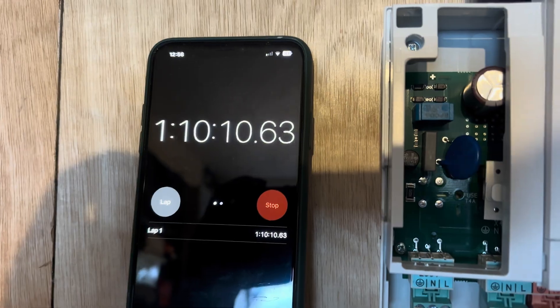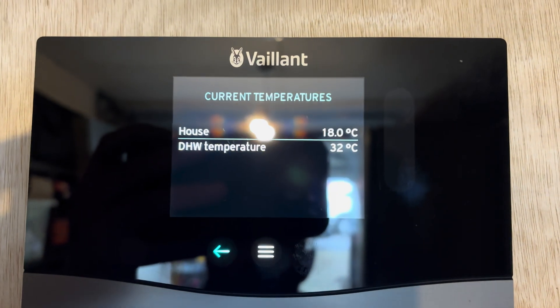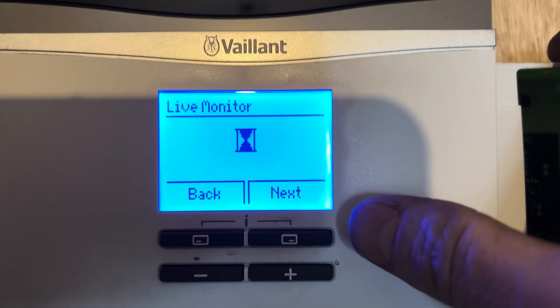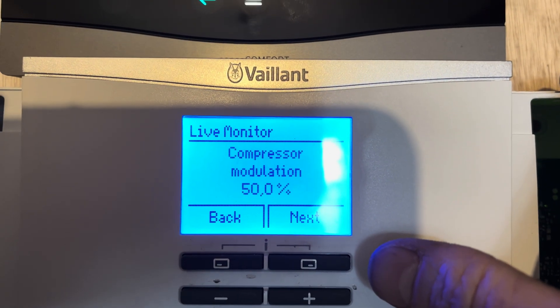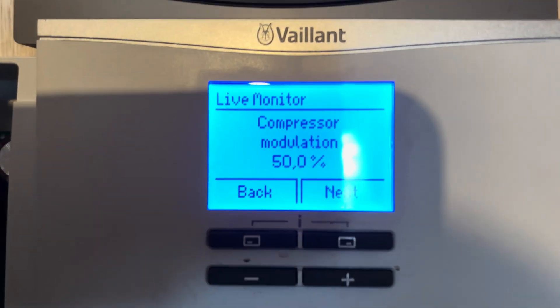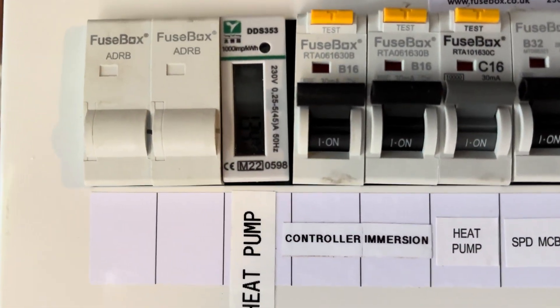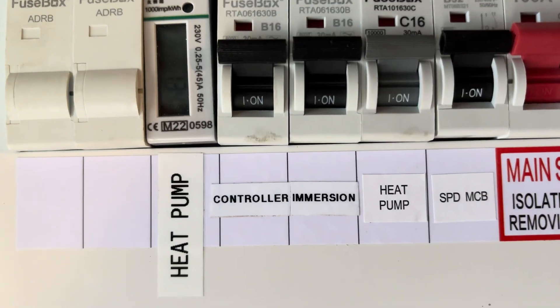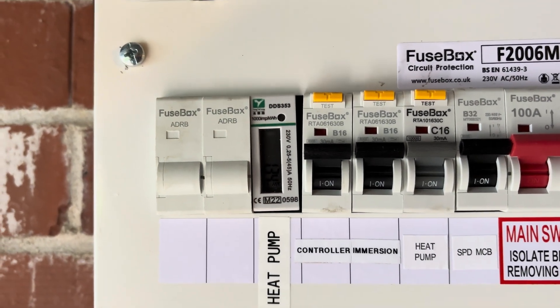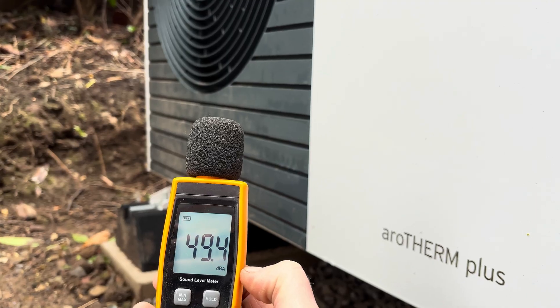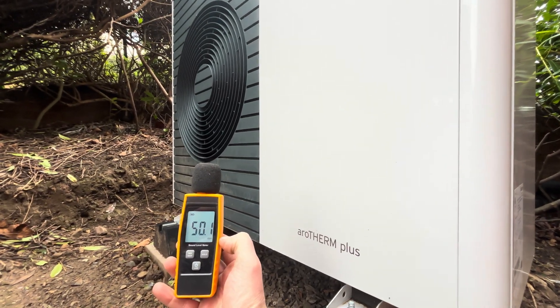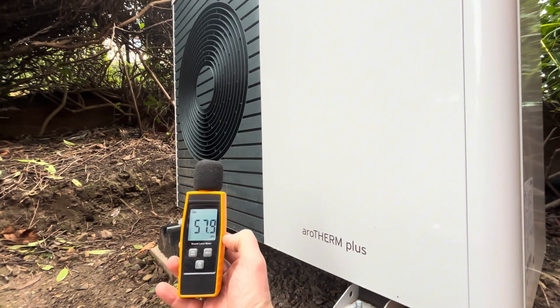1 hour 10 minutes in. Hot water temperature 32 degrees C. Power consumption 1.4. Modulation 50%. The electric meter is at 1.34 kilowatts. So that's not too bad really, starting from 11 degrees C. Still ticking over nice and quiet.